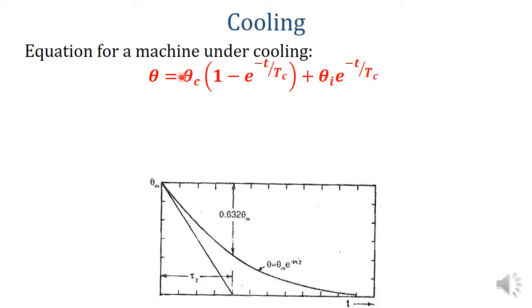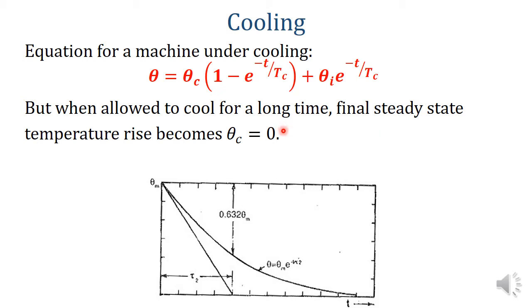Theta_c is the final steady state temperature rise after cooling, and theta_i is the initial temperature rise of the machine. When the machine is allowed to cool for a long time, its temperature reaches ambient temperature, so there is no difference between ambient and machine temperature. Thus theta_c becomes 0, and the cooling equation simplifies to theta equals theta_i times e raised to minus t by tc. This is the general cooling equation when the machine cools down to ambient temperature.